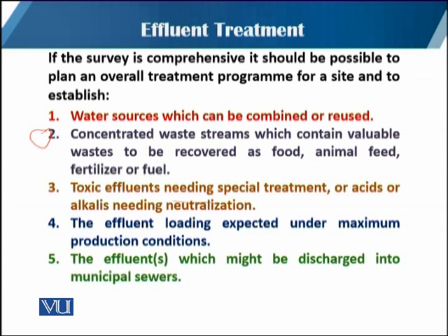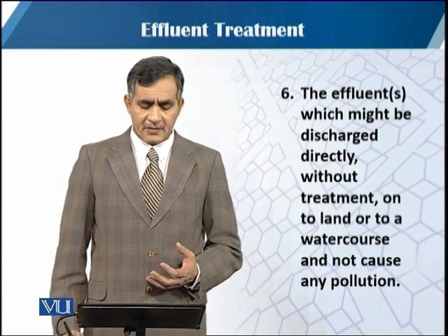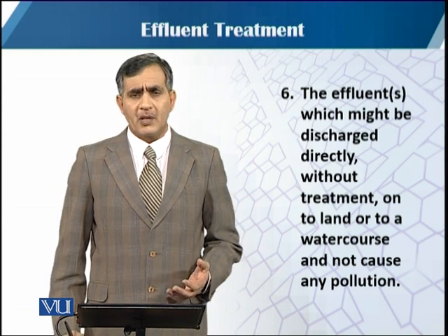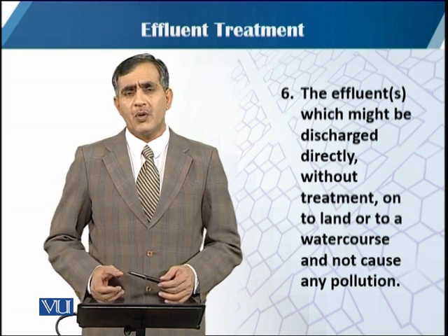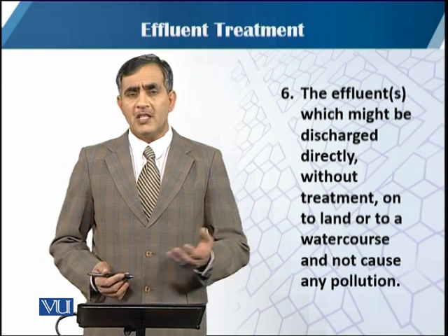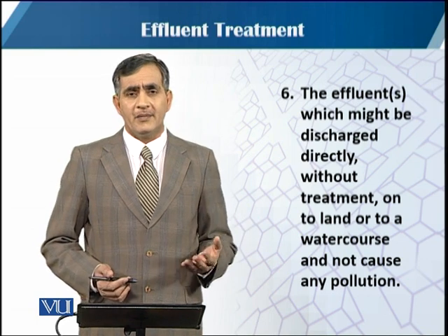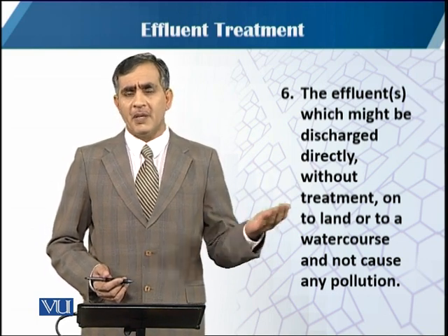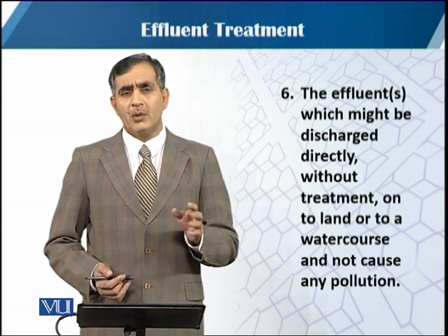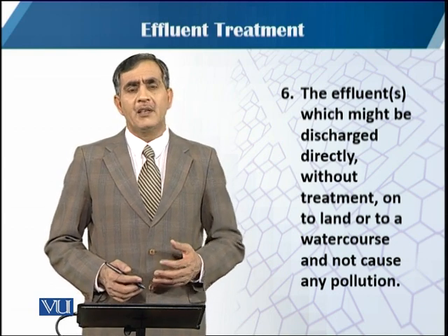Toxic effluents needing special treatment — such as acids or alkalis — need neutralization before being discharged into any water course. The effluent loading expected under maximum production conditions must be considered, since fermentation is mostly a batch process and during batch harvesting there is more discharge compared to normal days. The effluent may be discharged into the municipal sewer, or directly without treatment onto land or into a water course if there is no risk of pollution. The two basic options are either to discharge onto open land where water evaporates and residual material deposits on the soil, or to discharge into water channels.